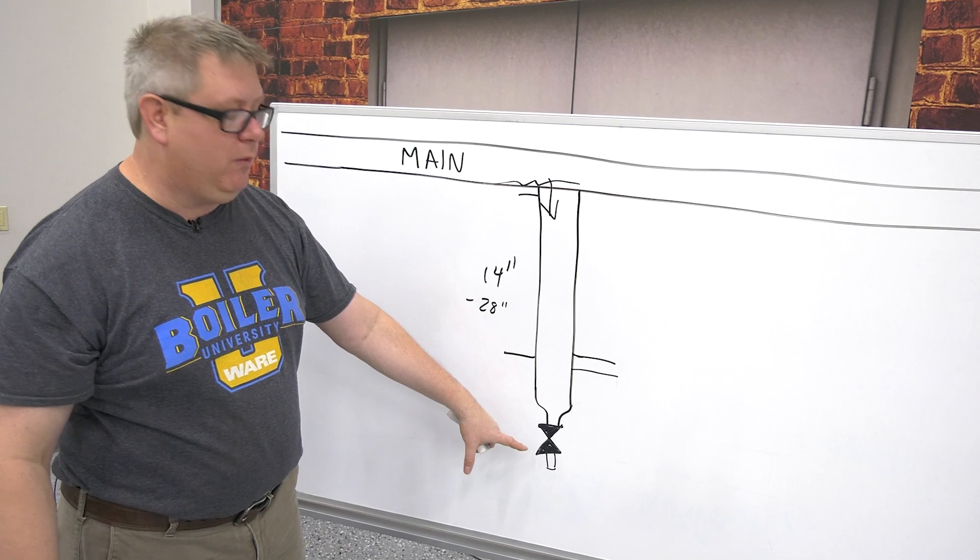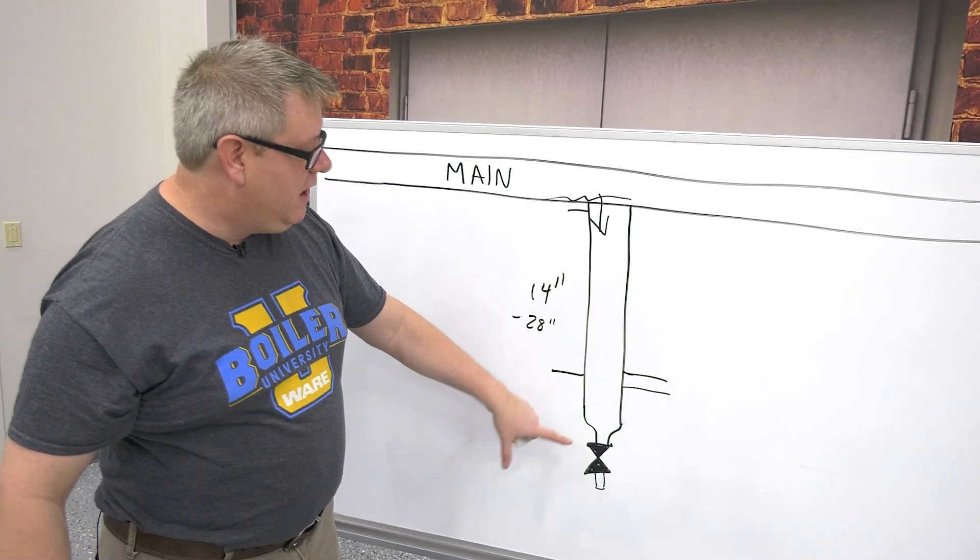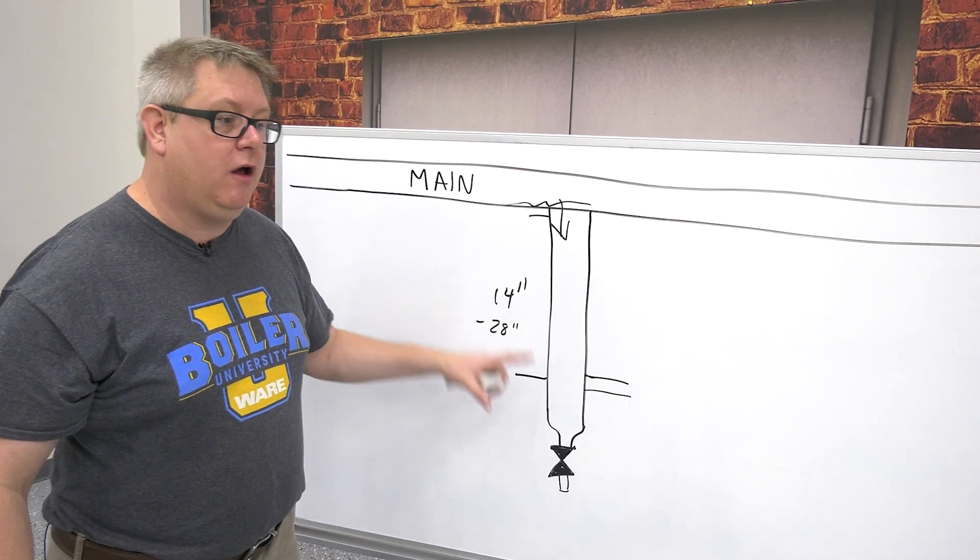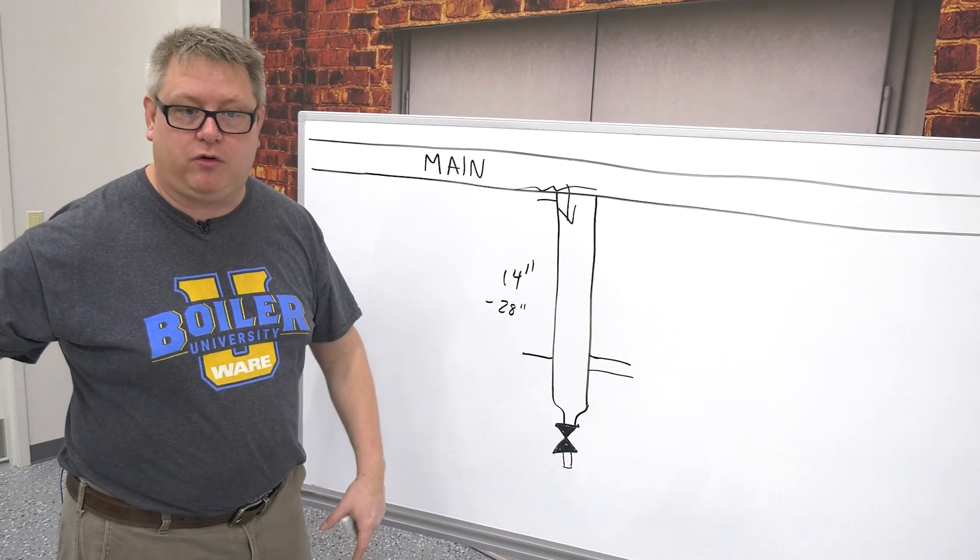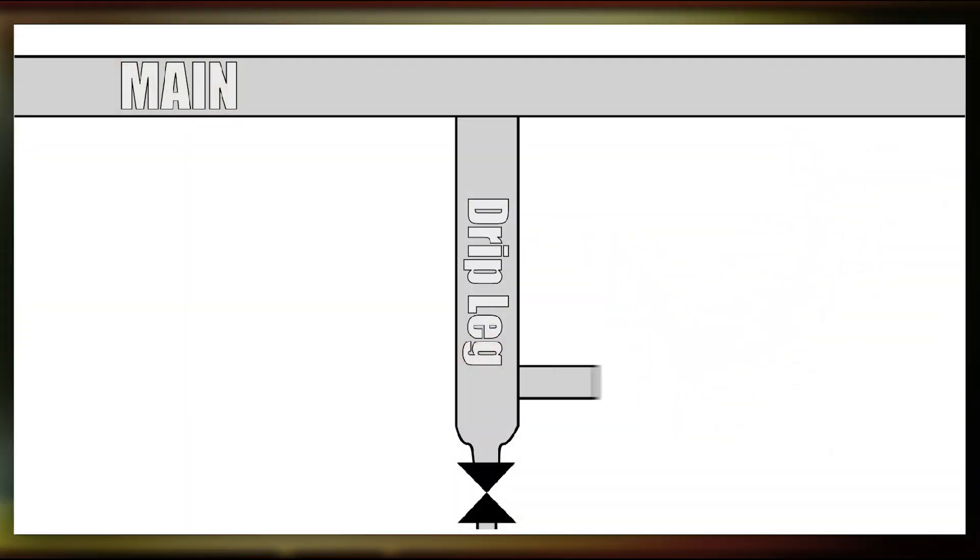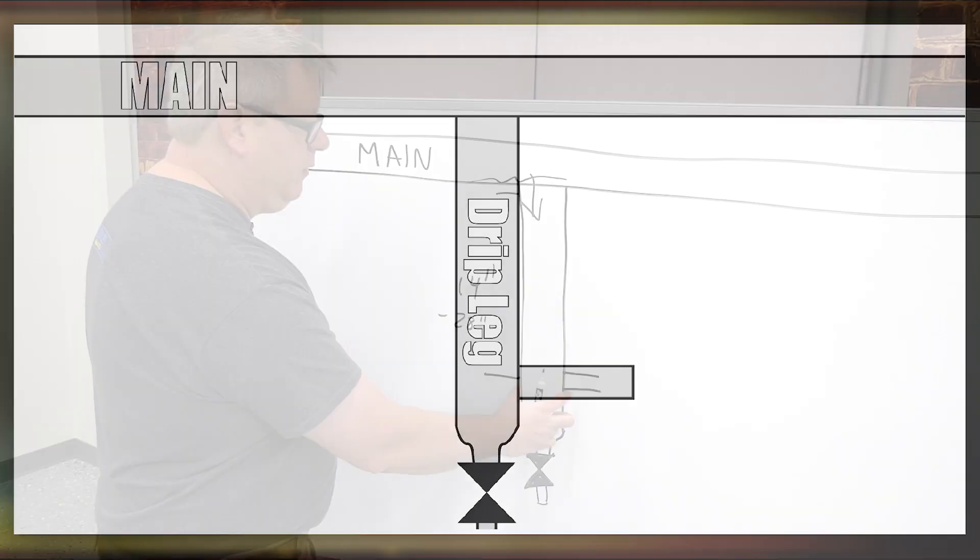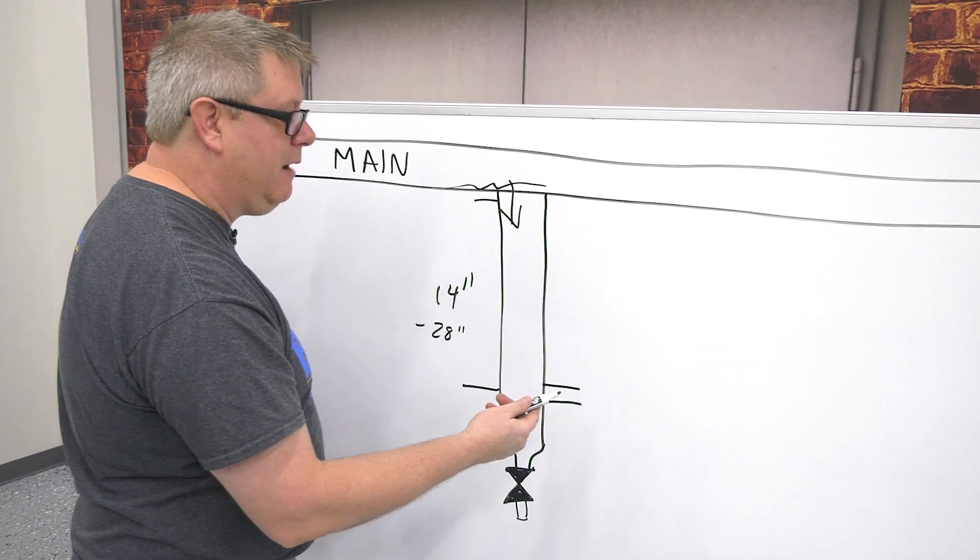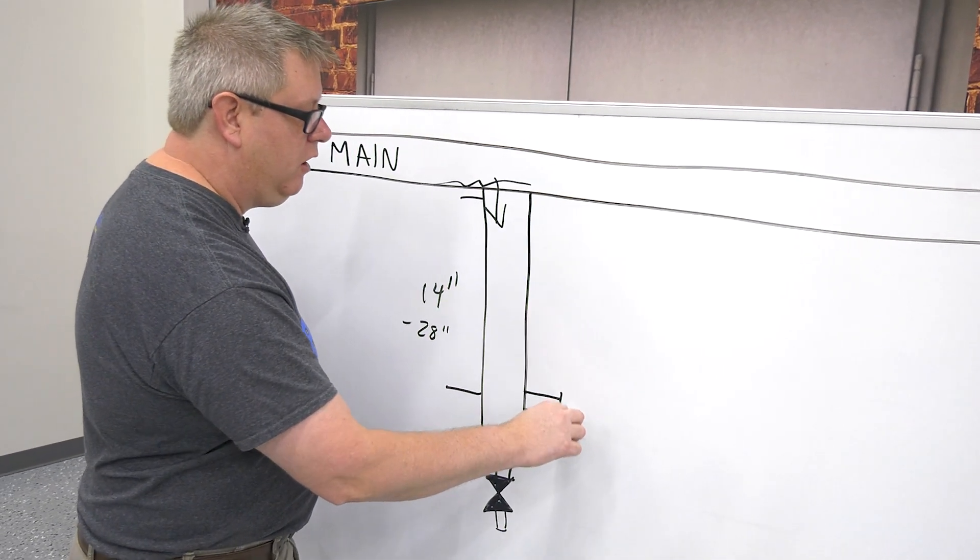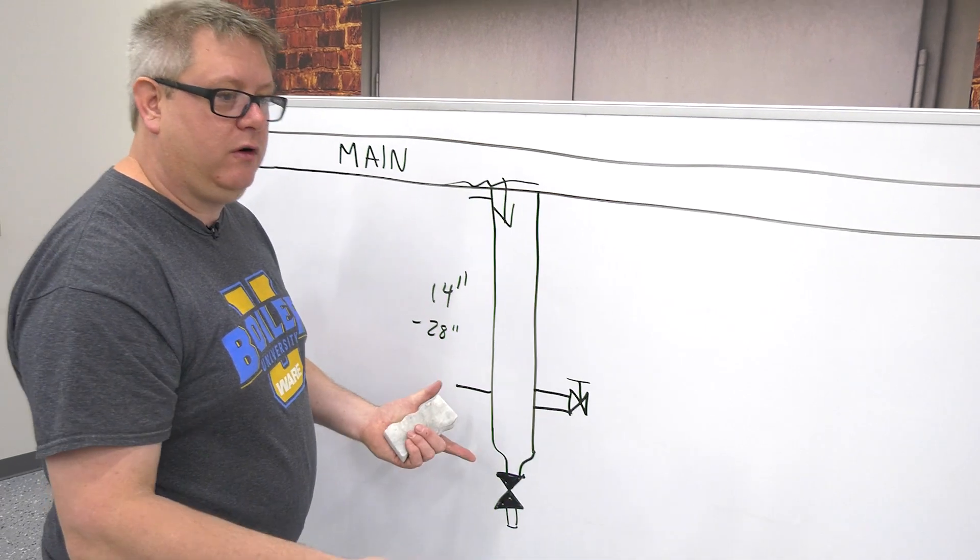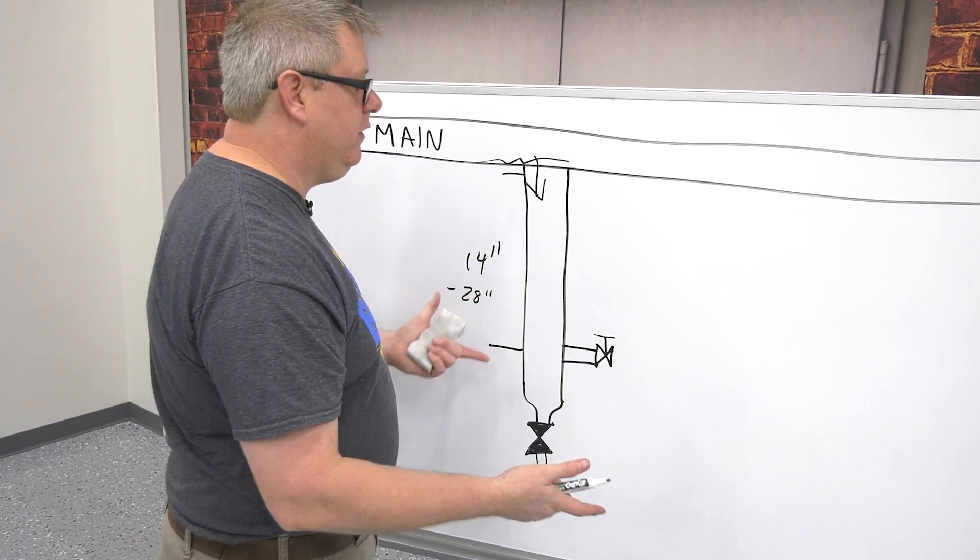So anytime we install a drip leg, we want to drain at the bottom, and in many cases we'll just have a drain and a plug in it. But we can also pipe that down to the floor ground level to make it more useful. So when we come off the side of the drip leg for our trap, we want to be off the bottom so we've got a pocket there for dirt so it doesn't go directly into our trap. And the first thing we're going to have on that takeoff for our trap is a manual isolation valve, and that's so we can service, do what we need to with this system.